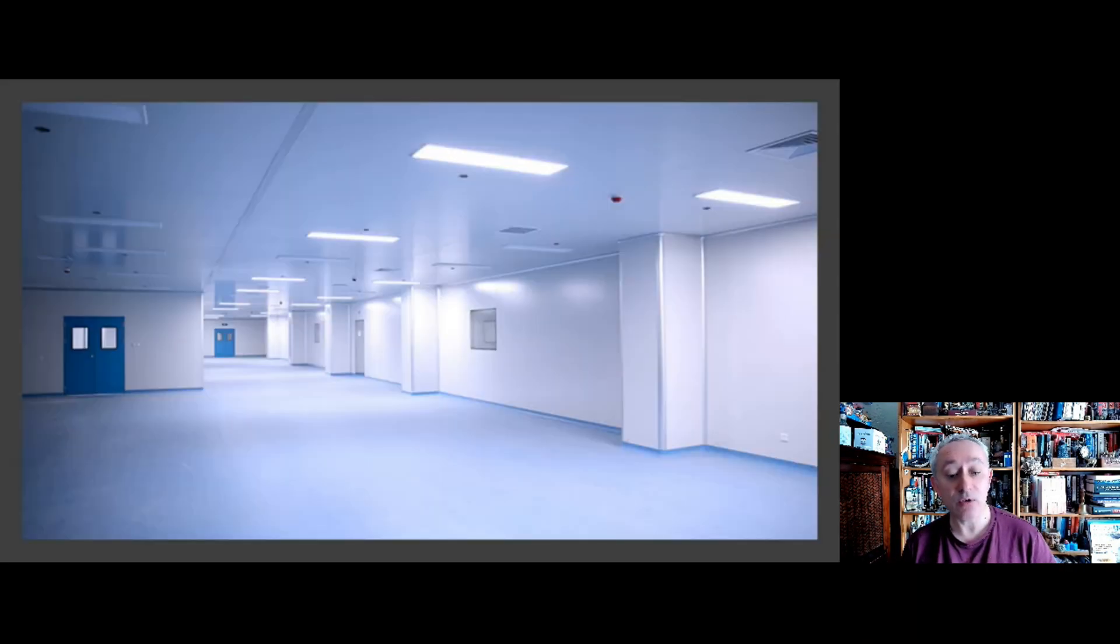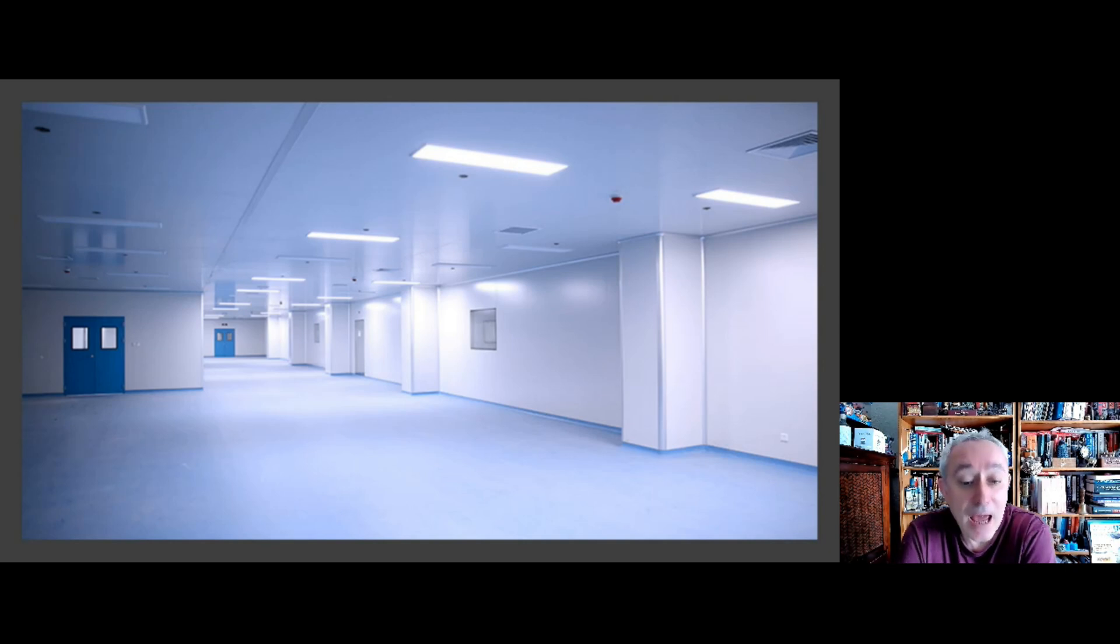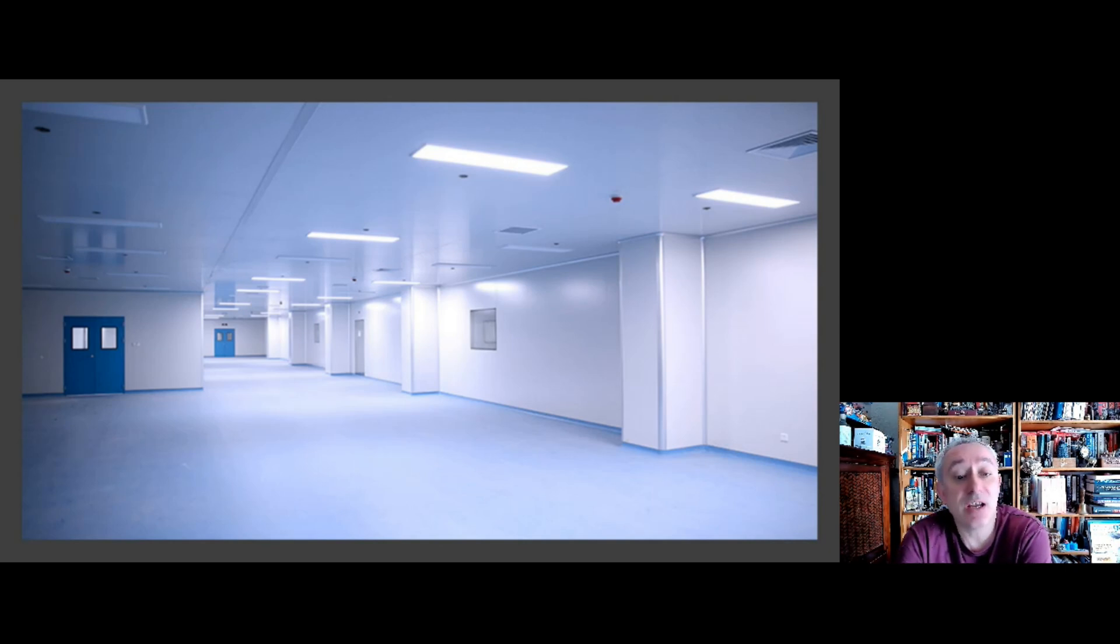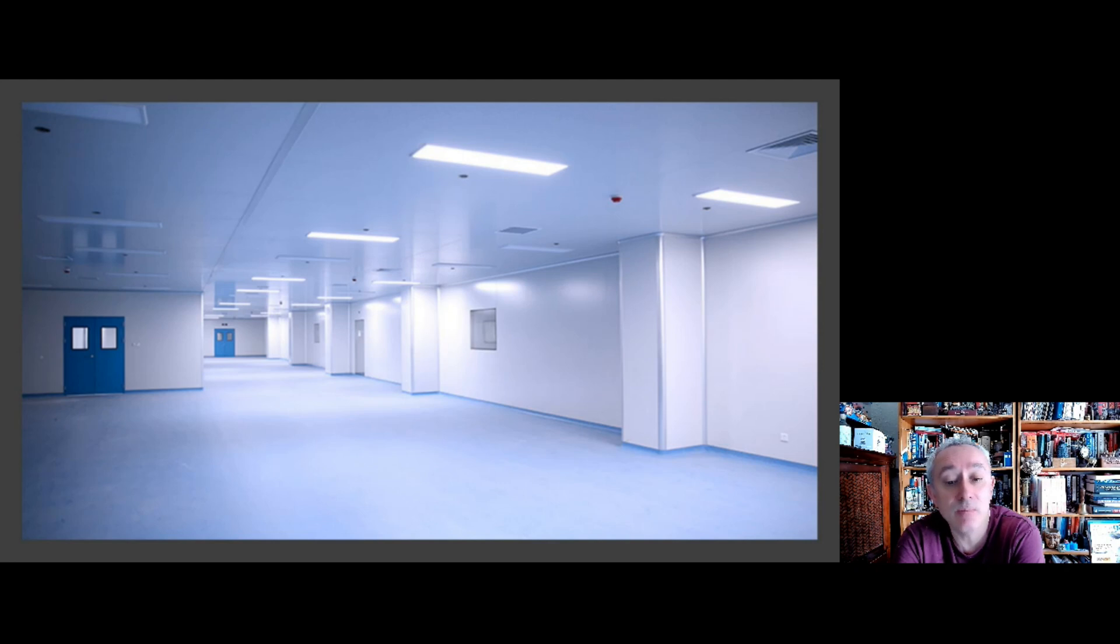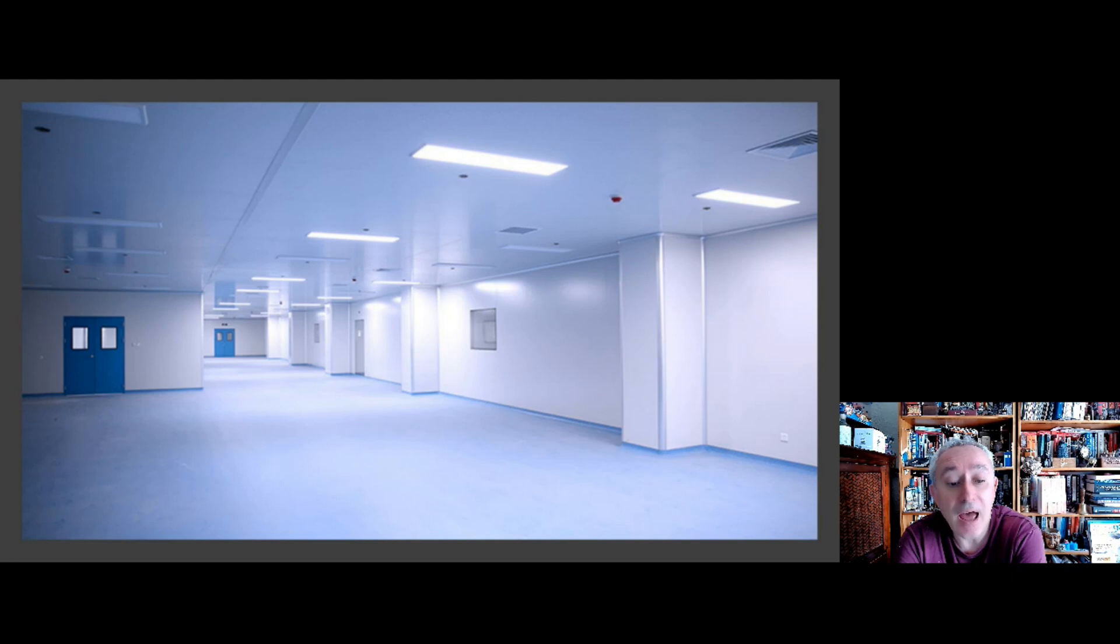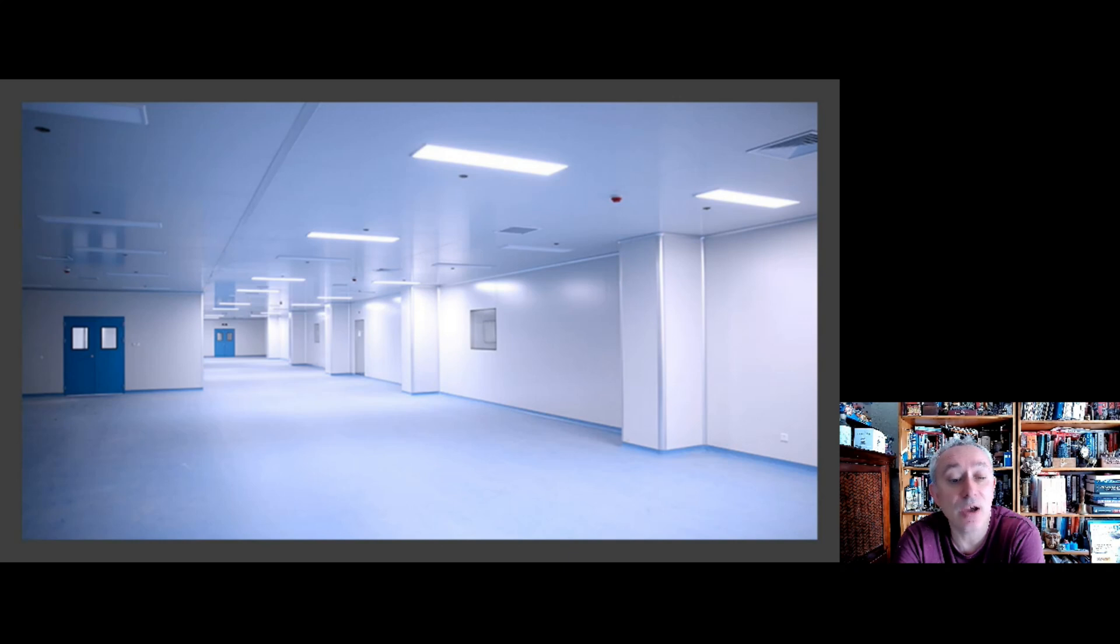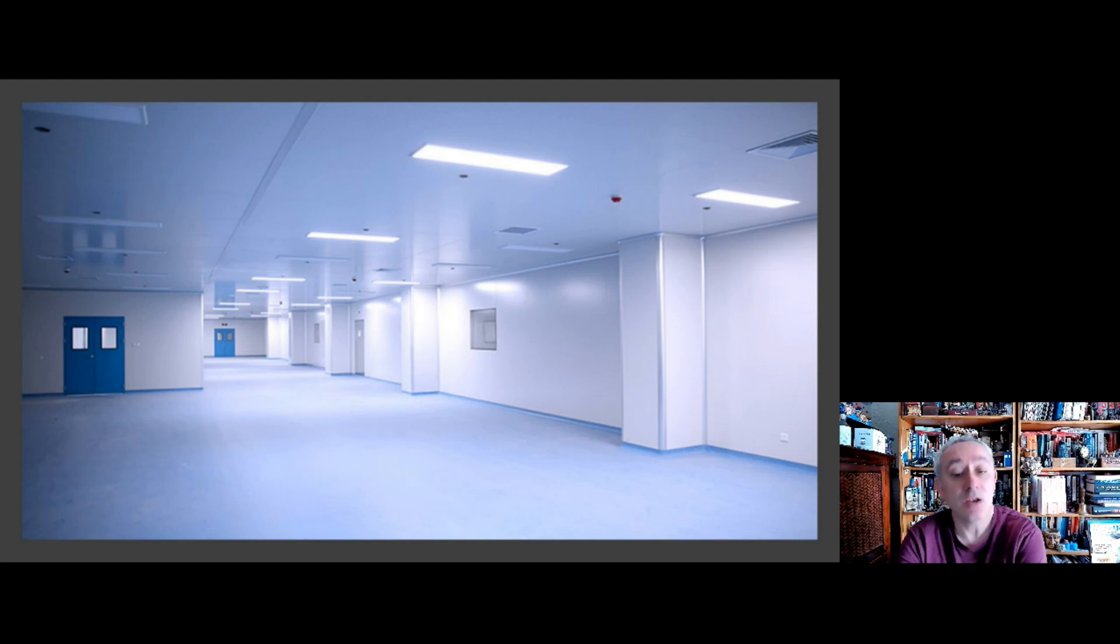But the HEPA filters that we use in pharmaceuticals and healthcare are of a different standard. HEPA stands for high efficiency particulate air filters, and there are two standards: there's a European standard EN 1822 or there's a global standard ISO 29463. The scale on the European is to have HEPA filters, the highest capacity which are H14 class filters, and these have a retention rate of 99.995% of 0.3 size micron particles.